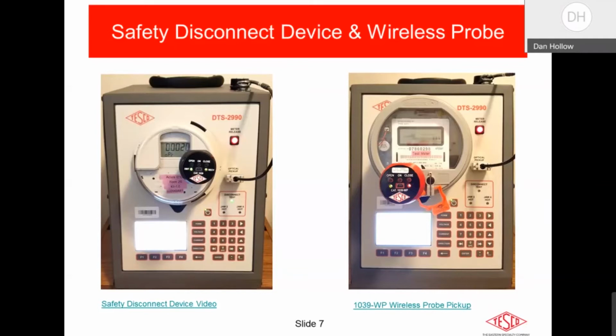So a lot of you out there have AMI systems. You're starting to purchase meters that have service disconnect switches in those meters. Those service disconnect switches allow you to remotely open or close that switch in the meter with the AMI head-end. And this allows you to turn customers off for non-payment and turn them back on when they come in and pay their bill without having to roll a truck and go out there and pull the meter and boot it, or pull the meter and put in a meter cover.